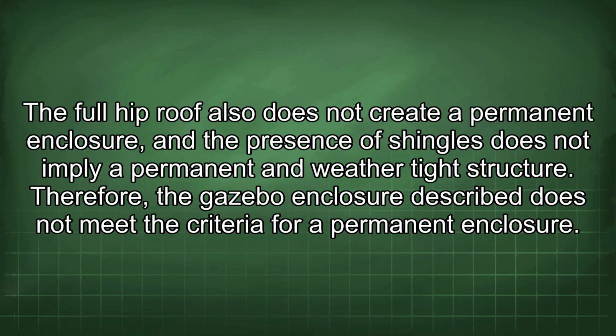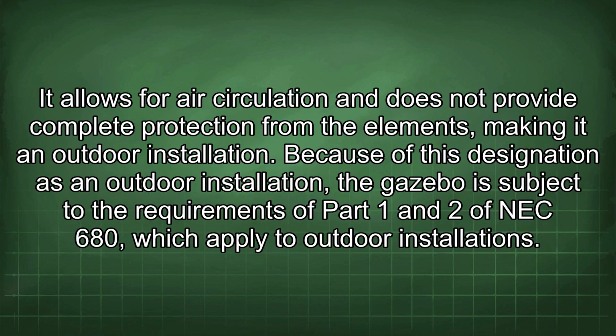The full hip roof also does not create a permanent enclosure, and the presence of shingles does not imply a permanent and weather-tight structure. Therefore, the gazebo enclosure described does not meet the criteria for a permanent enclosure. It allows for air circulation and does not provide complete protection from the elements, making it an outdoor installation.